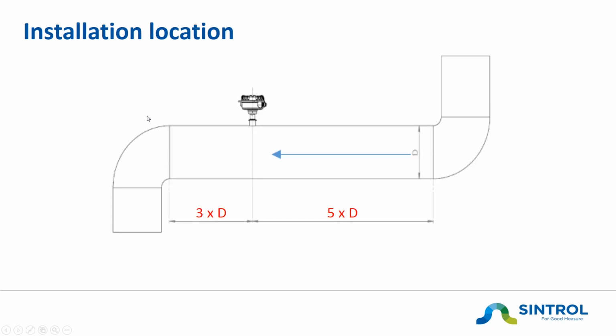Installation location. Please make sure that you install our instrument in a straight piece of duct perpendicular to the flow. We recommend to be about 5 times the diameter away from any bend or diffusers or whatever, upstream, and about 3 times the diameter downstream from the measurement point.